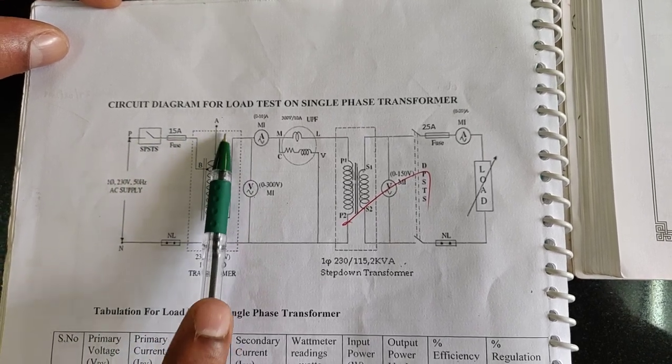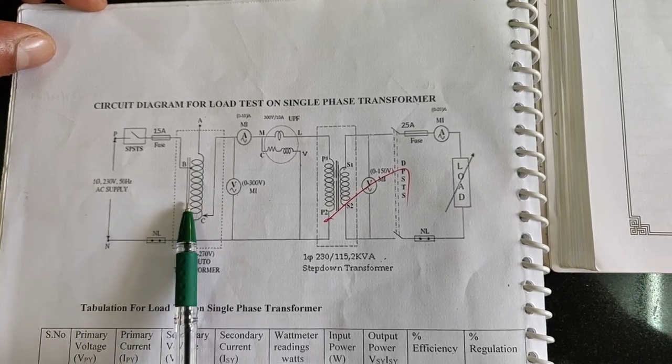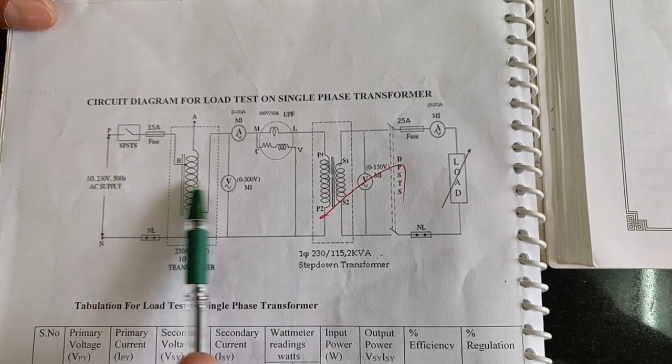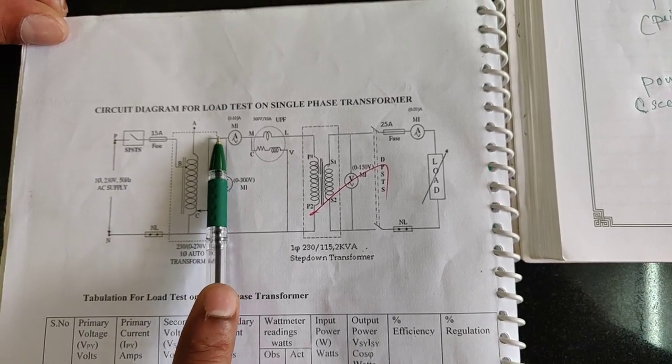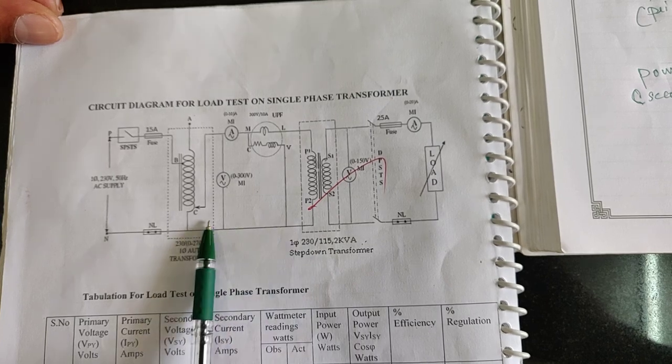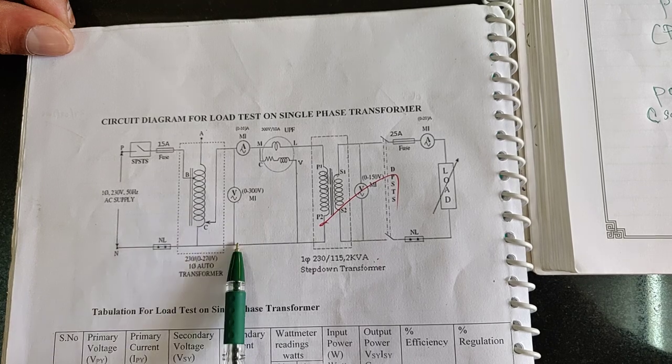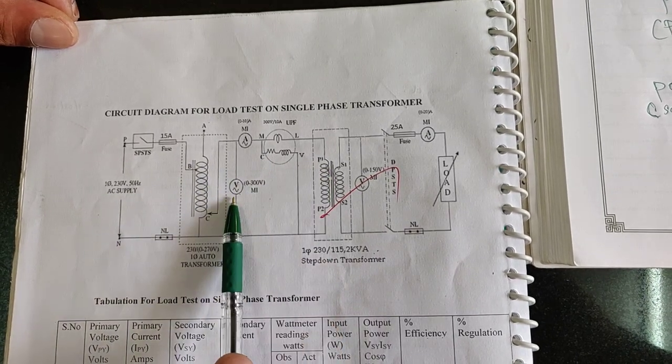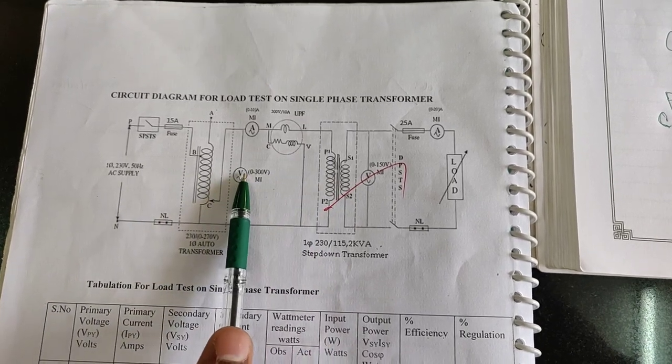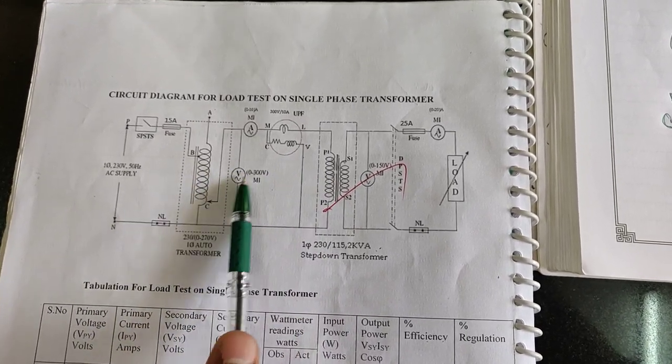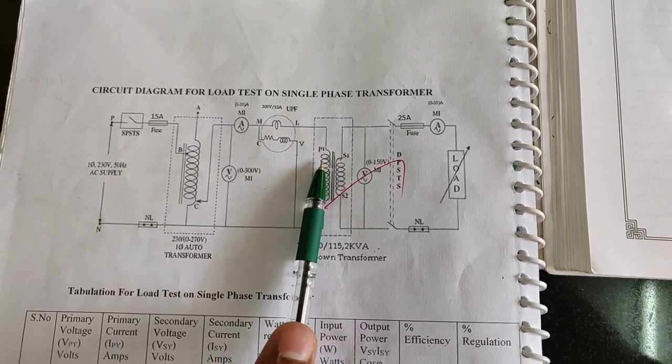The same supply is given to the transformer which is called auto transformer or we will call it as single phase variac which will give the variable voltage. The output of this transformer is the variable voltage is given to the transformer primary side via an ammeter and a wattmeter and also a voltmeter is connected across the primary coil to measure the primary voltage otherwise the high voltage and this ammeter is used to measure the primary current consumed by the transformer.